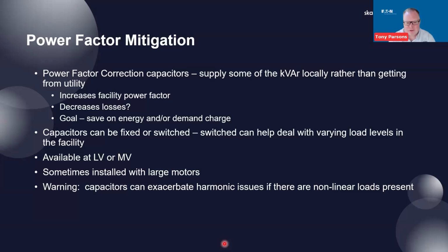Capacitors can be either fixed or switched. Fixed, you turn them on and there they are. The switched may have automatic means to switch different stages in and out, and that can help if you have widely varying load levels in your facility. Generally you don't want to overcorrect when load is light, maybe overnight or on the weekends. So if you can bring in more capacitance when you need it and switch it out when it's not needed, that can be a help.